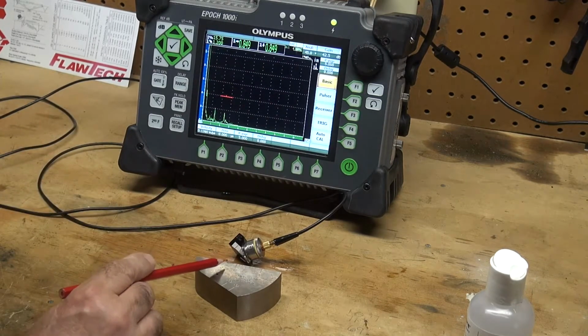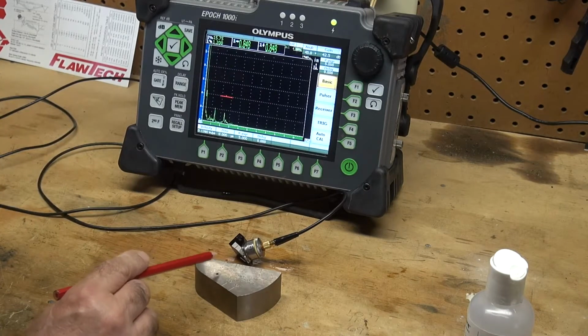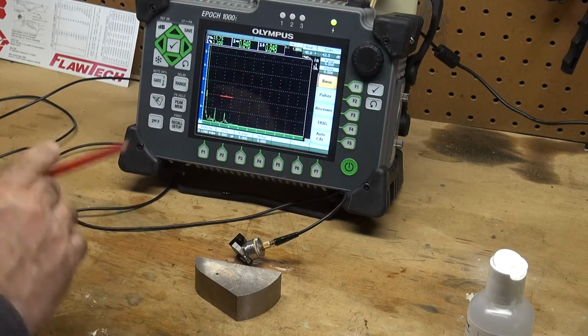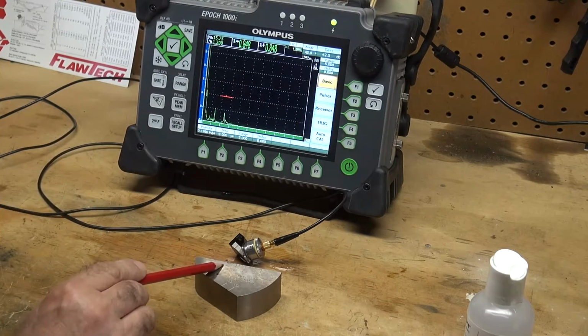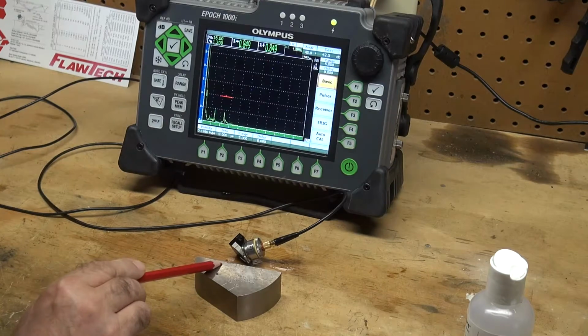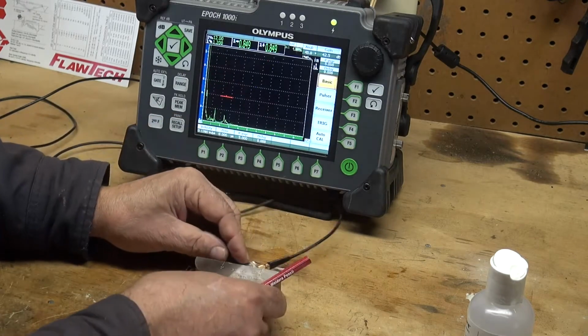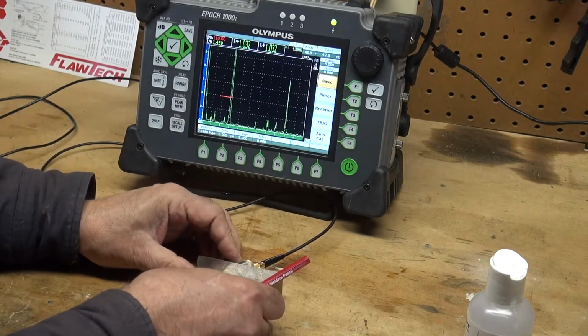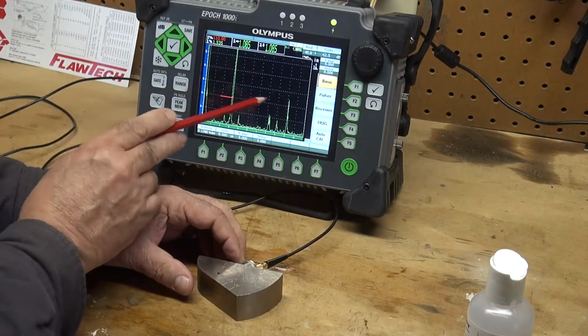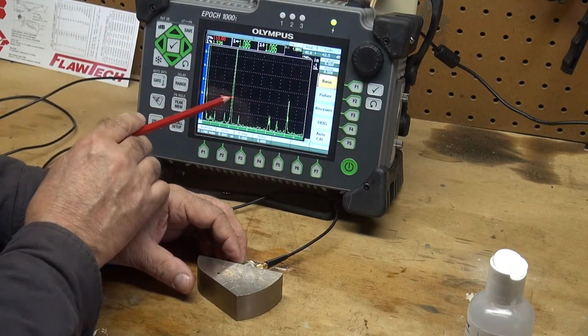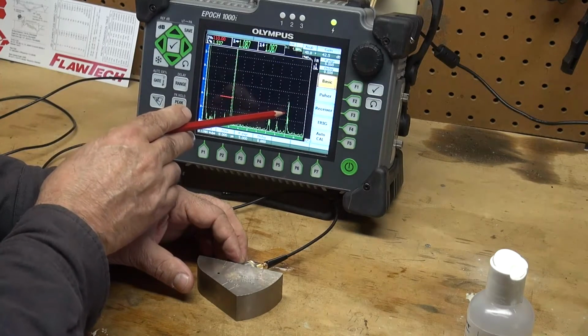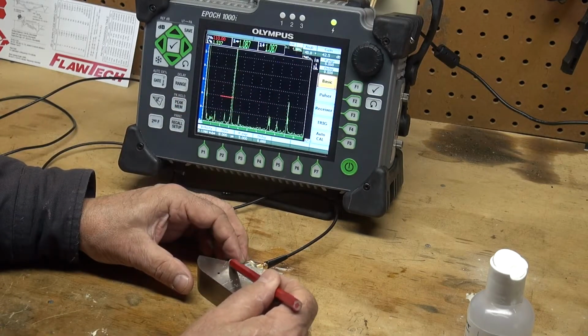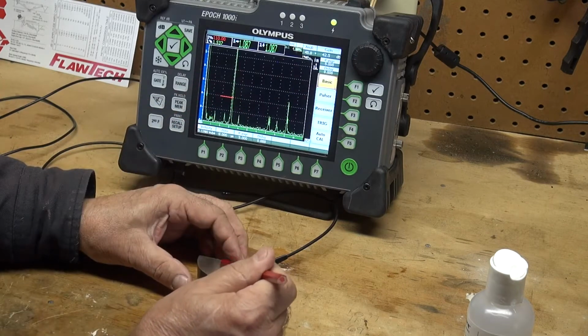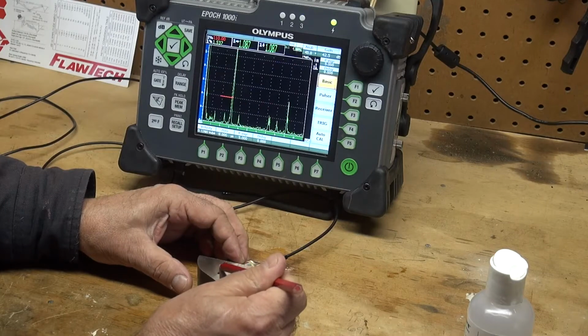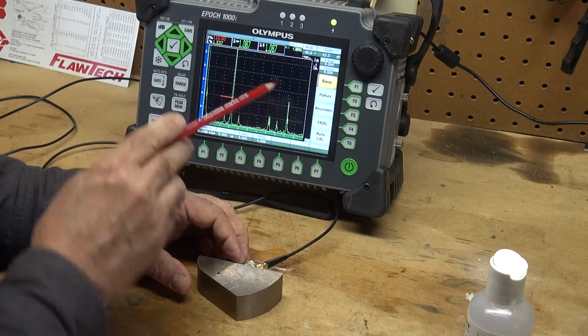And the Rompas block can be calibrated using a 1-inch and a 4-inch reflector. Here's the zero marking machined on the block. From the zero, we have 1 inch going to this radius. This radius is 2 inches. So I would put my transducer on here, and I will see a 1 inch and a 4-inch reflector. Because the sound goes, there's one, I'll get that reflector, that radius, 1 plus 2 is 3, plus 1 more is 4. So it comes up 1 and 4 inch.